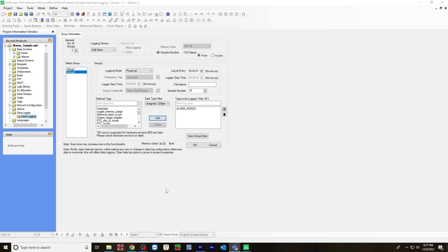Keep in mind, the reason why I'm using word registers to log is because you cannot log bools. You cannot log any of those alarm bools that we created earlier on. In IEC, you use discrete bools to trigger alarms, not bits within a word. You can trigger alarms with the values in a word. For example, if the temperature were to exceed a certain number, it would trigger an alarm. This word could then be sampled with data logging. That's why we use word registers instead of bools.